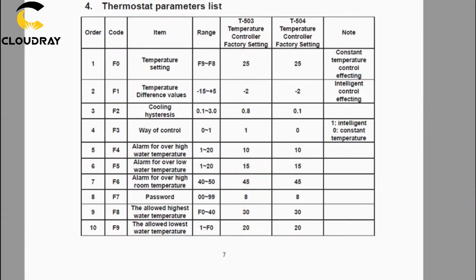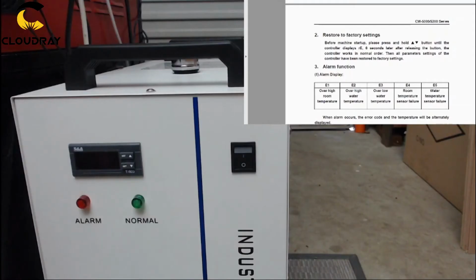First of all, I'm going to go into the settings in a moment. I'm going to show you how to do a factory reset to put everything back to default. And then I'll go in and change F3, the way of control. We'll set that to 0 so that it's constant temperature. And then the F0, we're going to set that at 18 degrees. So firstly, I'll need to change F9 to at least allow 17, 18 degrees, and then go back and change F0. And I'll go through that and we'll go and set that up.